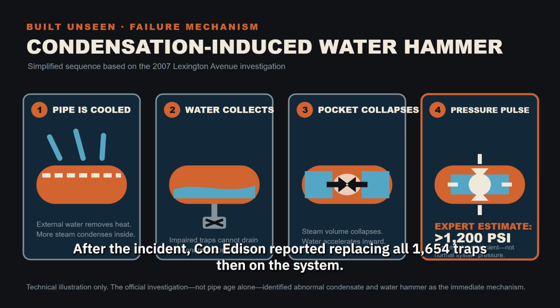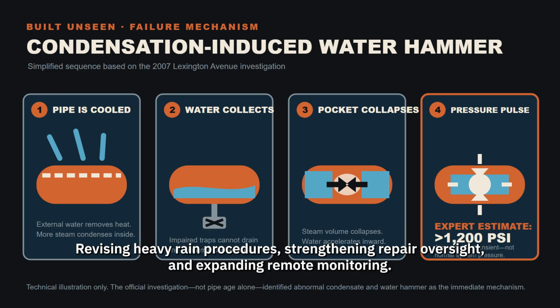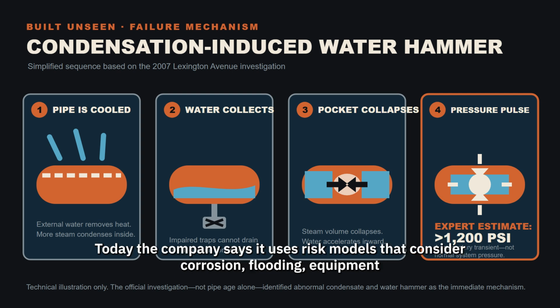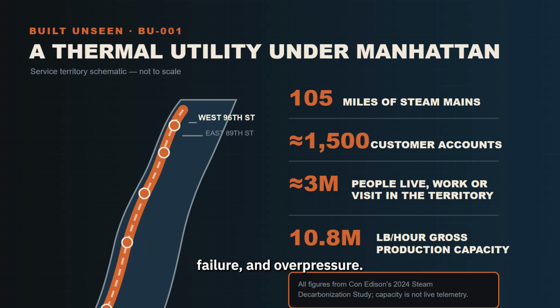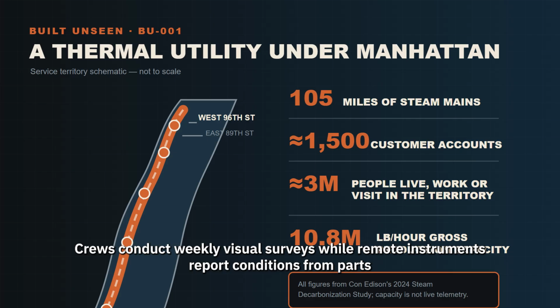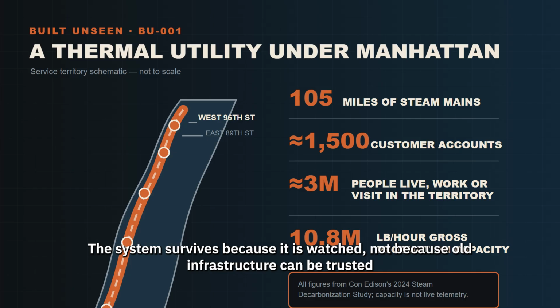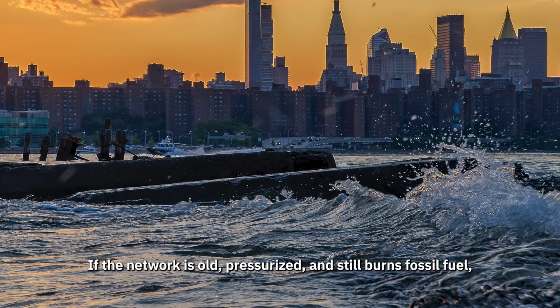After the incident, Con Edison reported replacing all 1,654 traps then on the system, revising heavy rain procedures, strengthening repair oversight, and expanding remote monitoring. Today, the company says it uses risk models that consider corrosion, flooding, equipment failure, and overpressure. Crews conduct weekly visual surveys, while remote instruments report conditions from parts of the network. The system survives because it is watched, not because old infrastructure can be trusted indefinitely. If the network is old, pressurized, and still burns fossil fuel, why not abandon it and electrify every building?